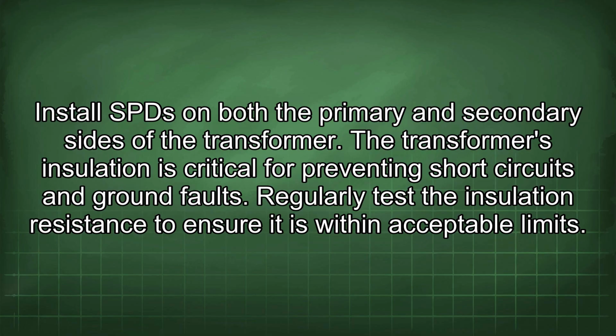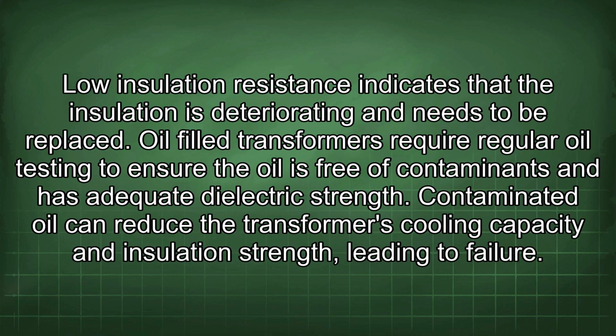The transformer's insulation is critical for preventing short circuits and ground faults. Regularly test the insulation resistance to ensure it is within acceptable limits. Low insulation resistance indicates that the insulation is deteriorating and needs to be replaced.